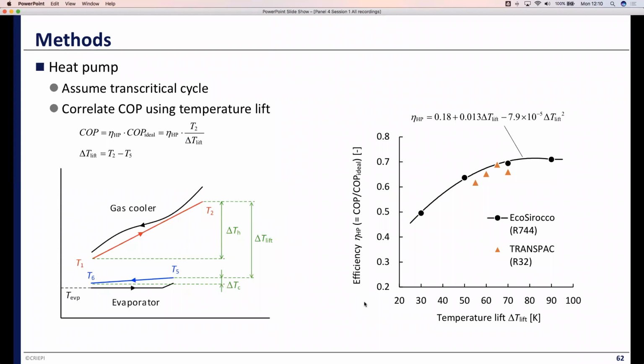From this slide, I explain the calculation method. Regarding the heat pump, we assume a transcritical cycle because the heat sink temperature glide, delta TH, is relatively high, and the heat source temperature glide, delta TC, is small because of latent heat recovery. We correlate the COP using the simple temperature lift, T2 minus T5.